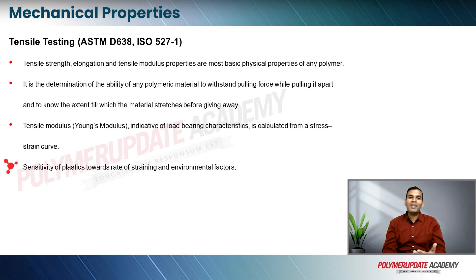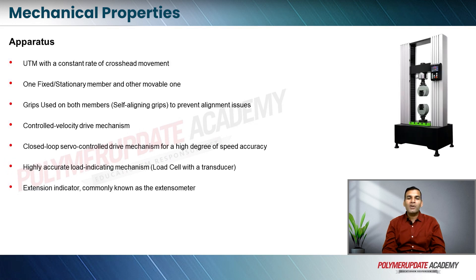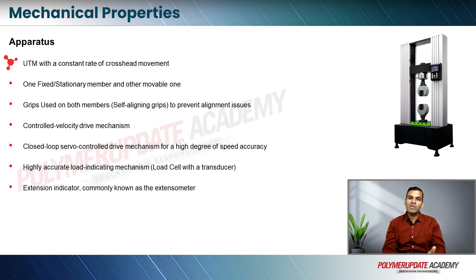Plastics are very sensitive towards the rate of straining and environmental factors. As you can see in the image, it denotes a UTM or universal testing machine. For tensile testing, the apparatus we are going to use is a universal testing machine and it should have a constant rate of crosshead movement.